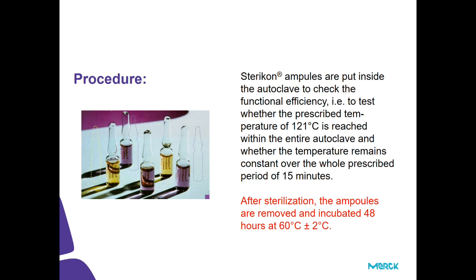As mentioned, the Sterikon ampoules are put inside the autoclave to check its functional efficiency. It means testing whether the prescribed temperature of 121 degrees Celsius is reached within the entire autoclave and whether the temperature remains constant over the whole prescribed period of 15 minutes. After this autoclave sterilization, the ampoules are removed and incubated for 48 hours at 60 degrees. And then we check if the color is changed or if the color remains unchanged.